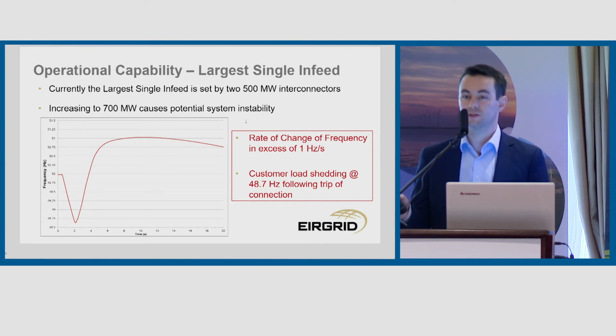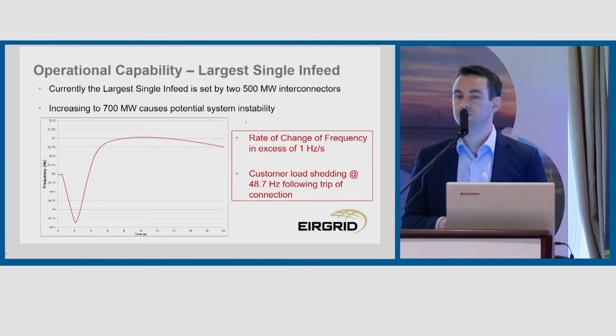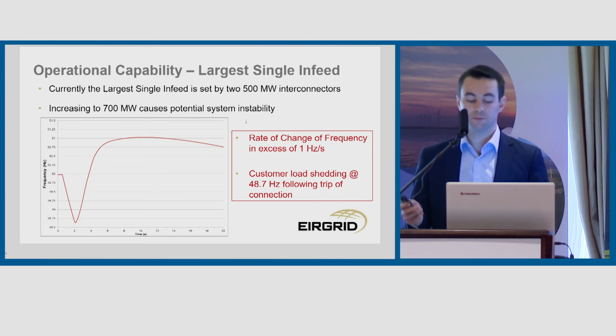However, if we increase this to taking 700 megawatts as an option, based on our current system and how our current thinking is carried out, we would see potential system instability if we were to lose this single connection point. We would see rates of change of frequency from 50 hertz at 1 hertz per second speed, which is in excess of our future operational capability. That would cause a lot of issues on the grid, and we'd very likely see customer load shedding.